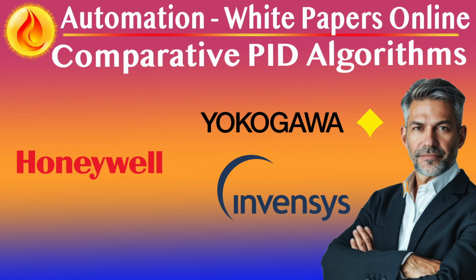Yokogawa provides explicit filtering controls. Engineers can filter PV signals directly and adjust the filter time constant independently of the derivative tuning. Additionally, derivative on PV only is standard in Yokogawa's PID blocks, which prevents overshoot during setpoint changes. In noise-sensitive environments, e.g. flow loops, pressure control, or fast-responding temperature systems, Yokogawa's fine-tuned filtering and D-action isolation offer stronger noise suppression and valve protection. Honeywell's approach is more accessible and sufficient in general-purpose applications where derivative use is moderate.